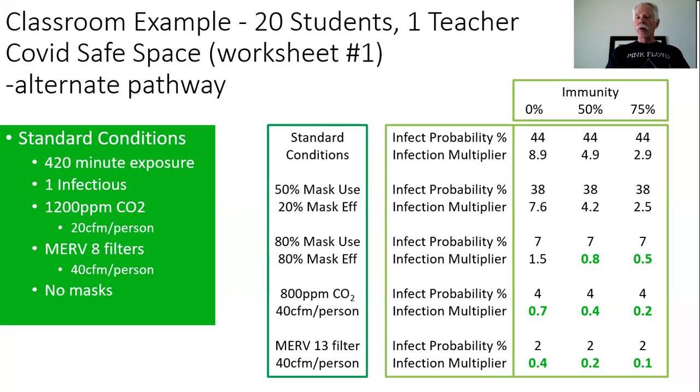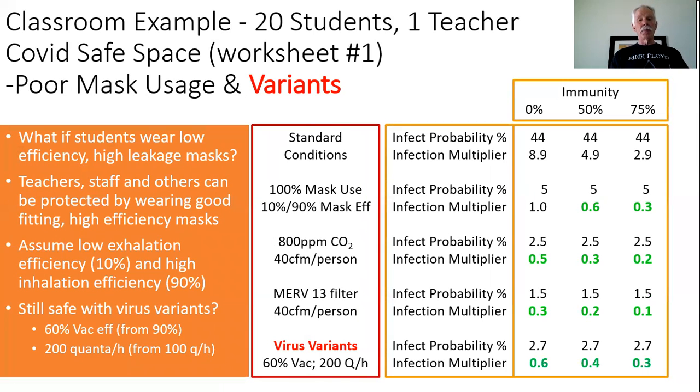And as we discuss air quality in other videos, there's other reasons why you want to increase fresh air above today's standards. That's why Walmart does it. That's why Kohl's does it. That's why any of your big box stores do it. If you measure the carbon dioxide level in them, they're already at 800 parts per million, while almost every other building around you is not. People perform better, they get sick less often, and they're more satisfied with the air quality. And the same is true in a classroom, and for the same reasons, you want that level of ventilation.